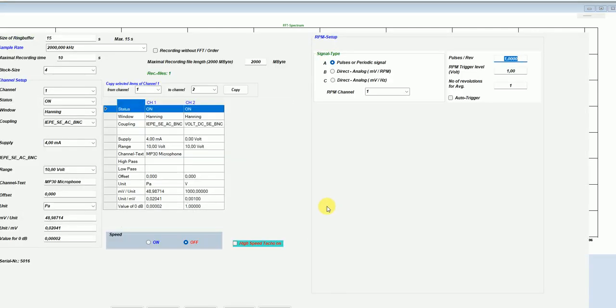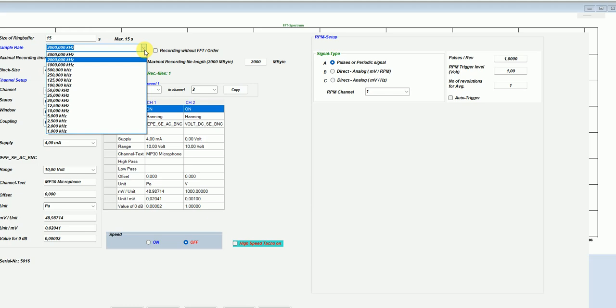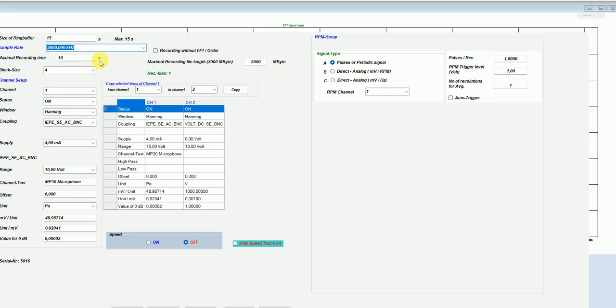Here we see the sample rates. The maximum sample rate of this system is 4 MHz, and I will be here at 2 MHz. In this case I have the microphone, so the IEPE current is now set to 4 milliampere. This is recommendable, especially if you have long coaxial cables, so 4 milliampere is a good setting. The input range is 10 volt and MP30 microphone. This is the unit.